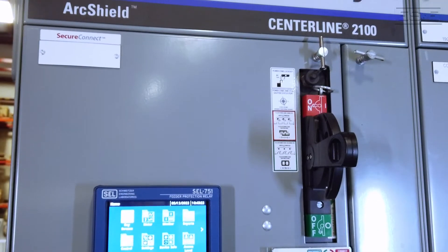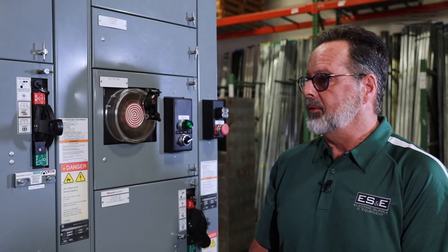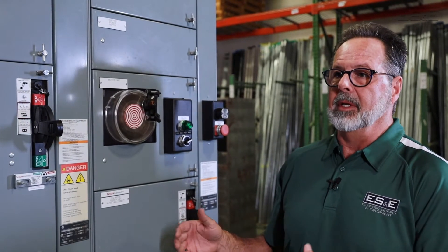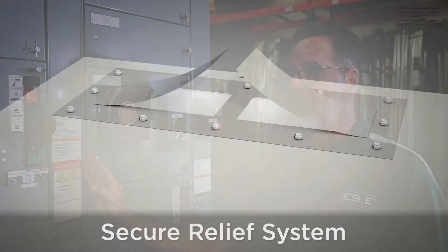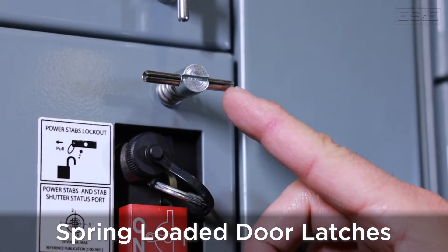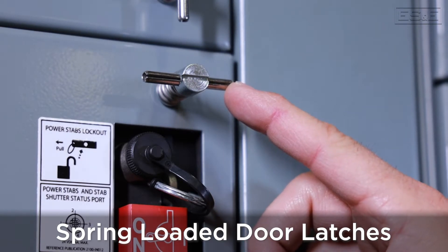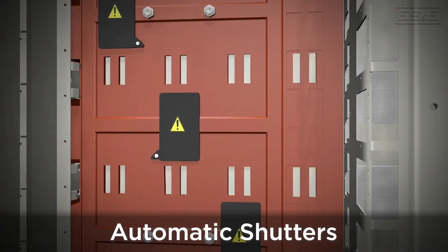We have a lot of customers that deal with safety and want to protect their employees, and I see up here that we have ArcShield. Can you tell me more about what ArcShield is? Allen Bradley's ArcShield system has features that will prevent personnel from being injured in the event of an arc flash. Protective features include double-walled steel insulation for added strength, a pressure relief system on top to allow expanded gases to be expelled, and spring-loaded door latches which allow gases inside a bucket to be released without blowing the door open. There are also automatic shutters which, when a bucket is pulled out, close to prevent any accidental touching of the vertical bus.